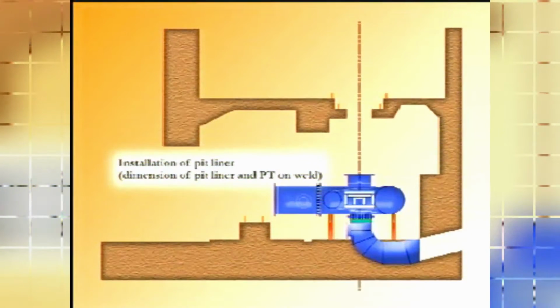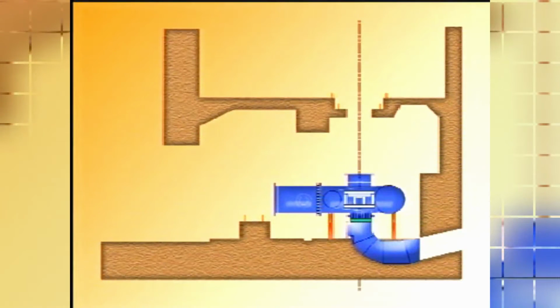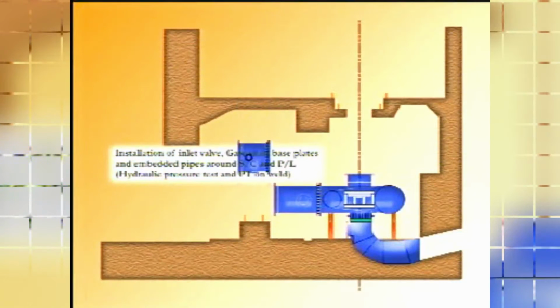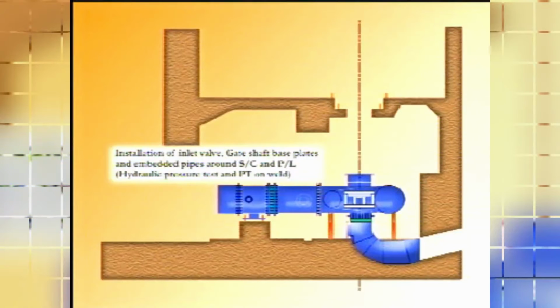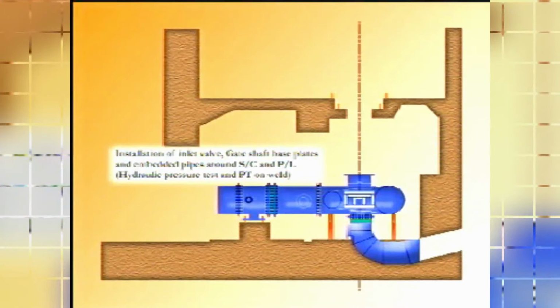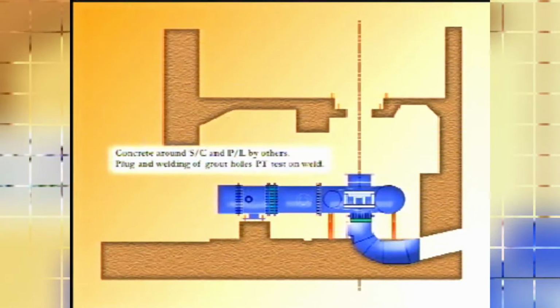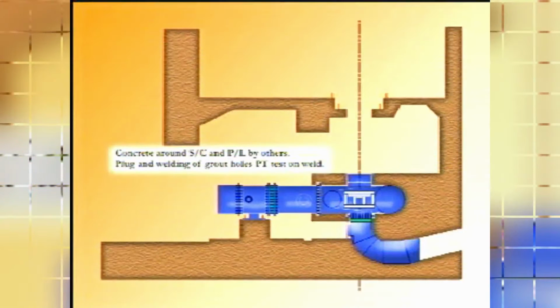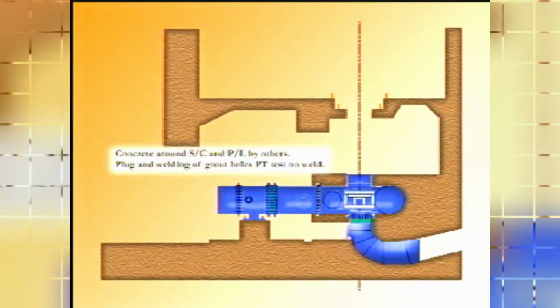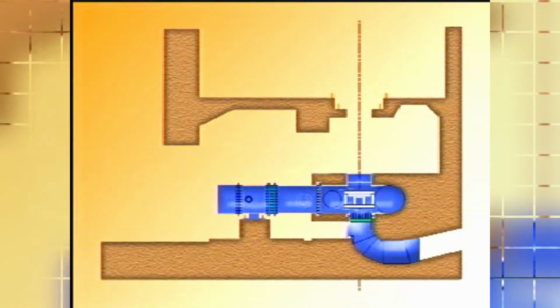Installation of pit liner. Dimension of pit liner and PT on weld. Installation of inlet valve, gate shaft base plates and embedded pipes around spiral case and pit liner, hydraulic pressure test and PT on weld. Concrete around spiral case and pit liner by others, plug and welding of grout holes, PT test on weld.